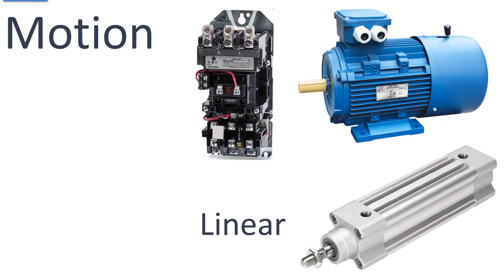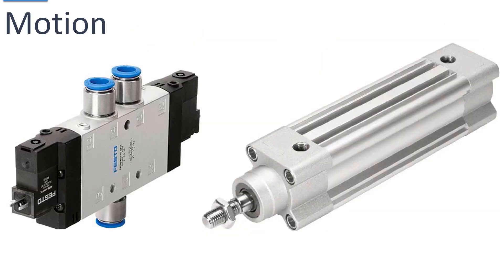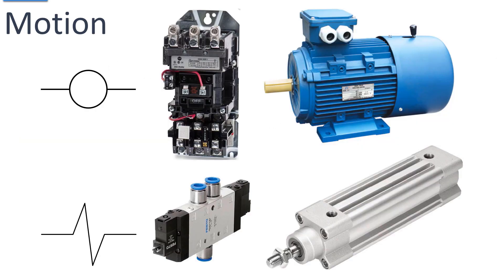Linear motion goes to either hydraulic or pneumatic cylinders. This is a pneumatic cylinder, and it uses a pneumatic solenoid valve. This valve has two solenoids on it, one on each end, and it electrically, by way of electromagnetic force, shifts a spool inside the valve body to control the direction of the cylinder. The symbol on prints for any coil, relay, starter, or otherwise is a circle with two lines. The solenoid symbol, even though that solenoid is actually a coil of wire, is drawn with this symbol.